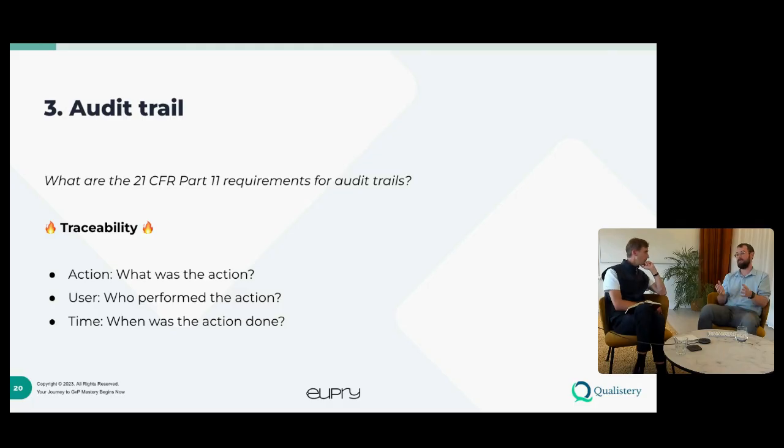One of the things we often see go wrong during audits is that you have a list of storage units, for example, that should have specific alarm settings. And then during an audit, of course, a customer audit or a regulatory audit always happens there, you see that the alarm settings are different or they've been changed. And who did that at what point in time? That could have been avoided by going through the audit trail.